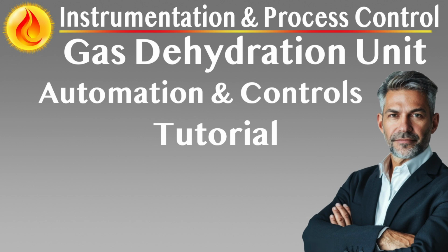Instrumentation design adheres to DEP and project-specific requirements for measurement, control, and protective functions and ensures compatibility with hazardous area classifications. Instrumentation scope and functionality. Glycol contactor monitoring and control. Gas flow and pressure control. Inlet gas flows through the contactor at a controlled pressure, typically managed via downstream pressure control valves. Flow is monitored upstream of these valves using calibrated flow elements and transmitters. Contactors situated between compressor stages rely on upstream and downstream compressor regulation for pressure control.